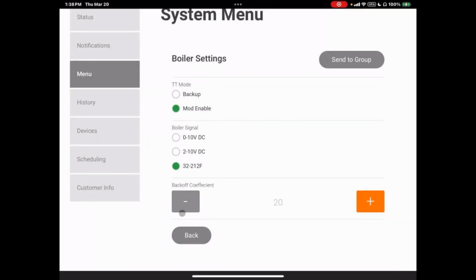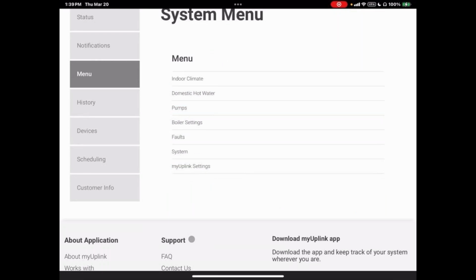And then we have a back off coefficient here. I wouldn't recommend messing with this setting, but essentially it fine tunes the boiler and how we back it off to maximize compressor operation and efficiency. We want the compressor to do as much as it can and bring the boiler in when it needs it and only when it needs it. Obviously, it's more efficient to run the heat pump than the boiler.